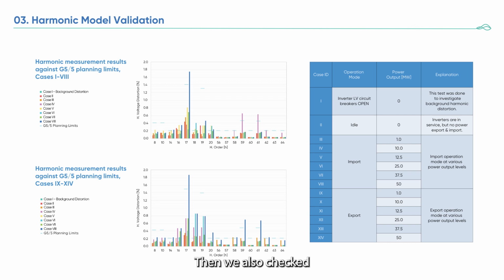Then we also checked with the LV circuit breakers open. Especially this mode was to check the impact of inverter self-impedance on the system, the tertiary kV system impedance. And as can be seen here, I think my laser is not working. As can be seen here, there were various non-compliances, which are mainly between the 14th and 20th order, and also there are a few between the 55th and 65th harmonic orders.